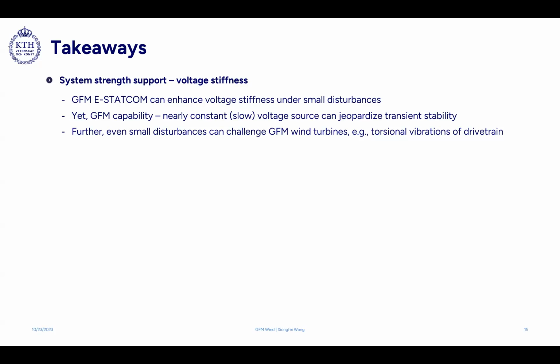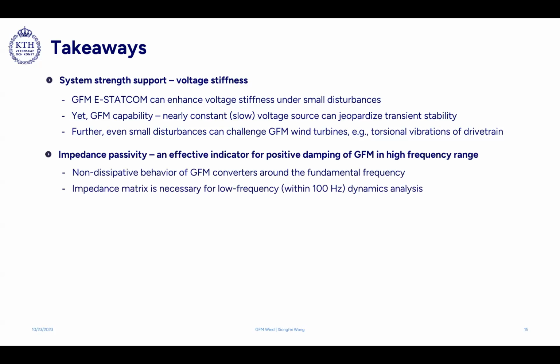And the third part is that even with small disturbances, the energy source dynamics or limits can also introduce some issues for the nearly constant voltage source, okay? And the second part is about impedance passivity. This is becoming a kind of industry practice for energy developers or the TSOs. It is an effective indicator for positive damping of grid forming in the high frequency range. This high frequency means about 100 Hertz.